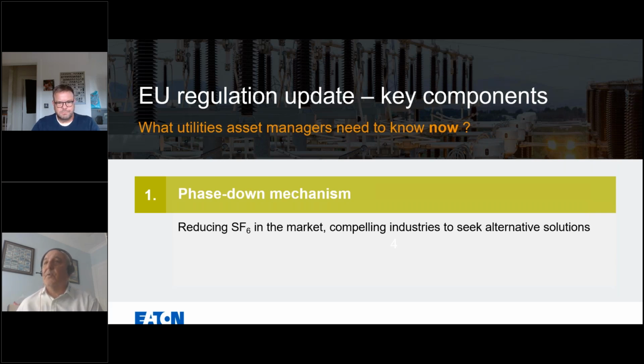Companies must explore SF6-free alternatives to comply with these reduced quota limits. This may be applicable to switchgear that, whilst not failed, is reaching its end of life and should be replaced. There are many solutions available currently up to 24 kV.